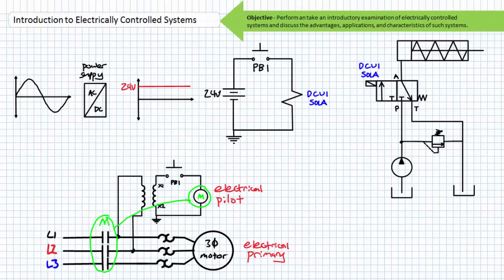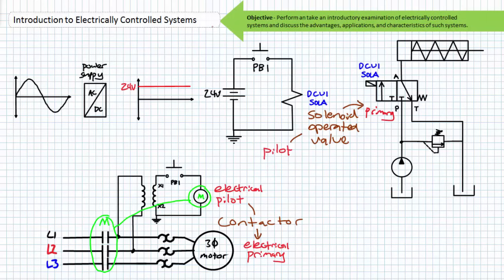Coils are typically represented as a circle in the control schematic. The label inside the coil, M, clearly designates that this coil controls contactor M in the primary schematic and serves as the principal interaction point between the pilot and primary aspects of this electrically controlled motor system. There are obvious differences between them, but if you want to think of it this way, a coil magnetically linked with a contactor is analogous to a solenoid-operated directional control valve.